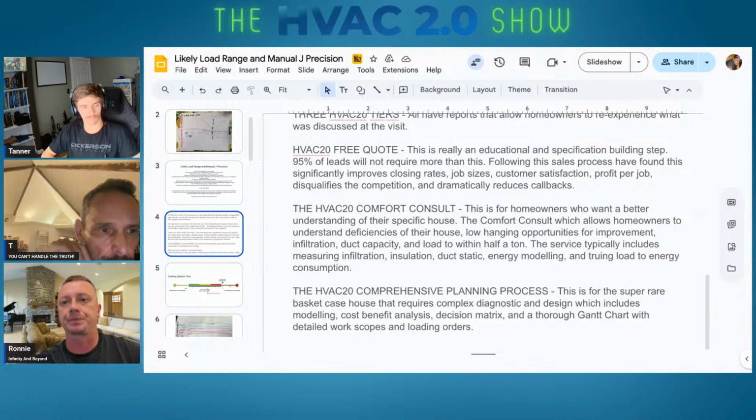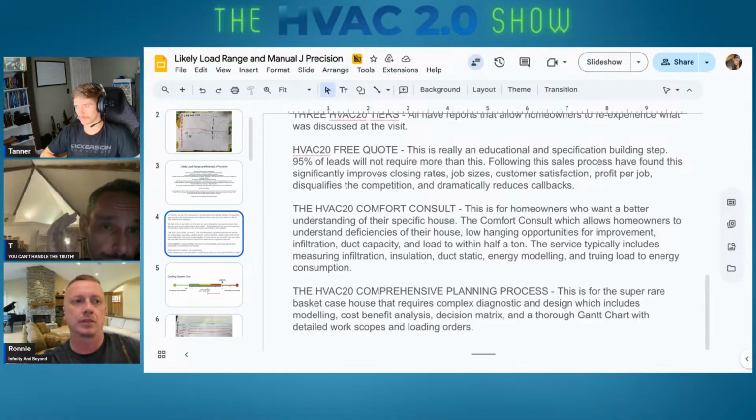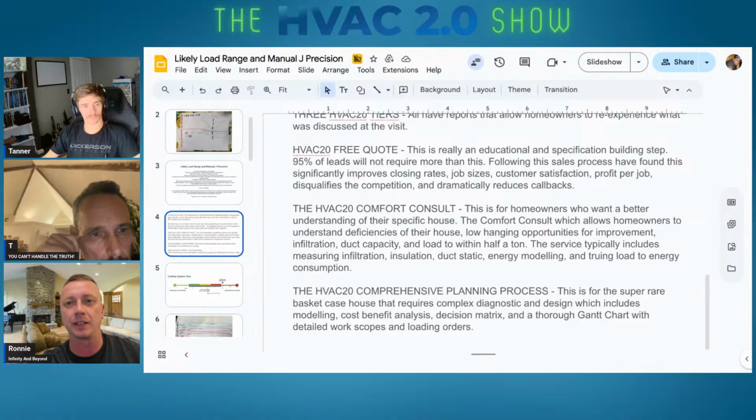You had to increase your thermostat set point because everybody was cold. Yeah, and it's 74 in here now. We've always kept it 70, 72. Also, I think you told me that you have reheat set for something pretty low, like 48%. I did. I bumped it up to 50. But it never even gets close to that because it was running at 38. Yes, and 40 and stuff like that. On rainy days, it'll get close to 50, and it'll use a little bit of that. But since I've turned reheat on 2 months ago, I've used like $1.50 in reheat.